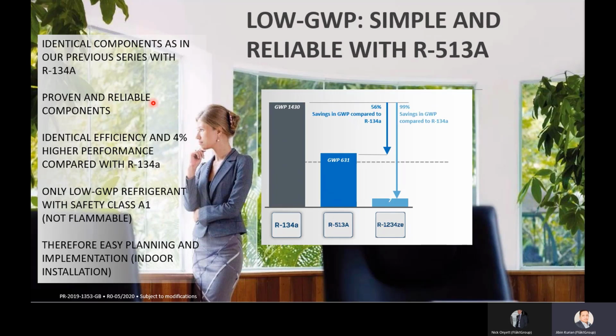How does it compare to the current R134A? R513A has a GWP 56% lower than R134A, and R1234ze has approximately 99% lower GWP than R134A. So theoretically, R513A and R1234ze are the future refrigerants. Again, we use identical components as in our previous series with R134A. It has identical efficiency and 4% higher performance compared with R134A. As I said, R513A is classified as an A1 non-flammable gas.